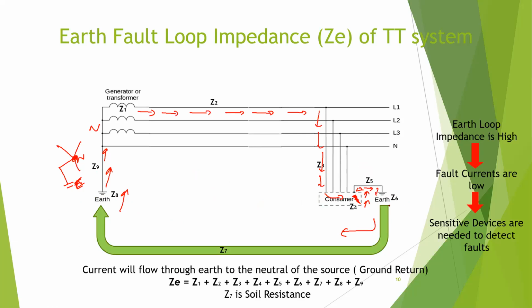So you will see these things in the industry. You will set a meter and measure the earth. This one is called earth electrode resistance. So this is earth loop impedance. So earth electrode resistance, we are keeping that at somewhere around 10 ohms. Usually this can be much higher depending on your soil and your earthing system. If you have only one rod, this will be very high. That can happen, but usually in the installation in a TT system, our recommended value is 10 ohms.